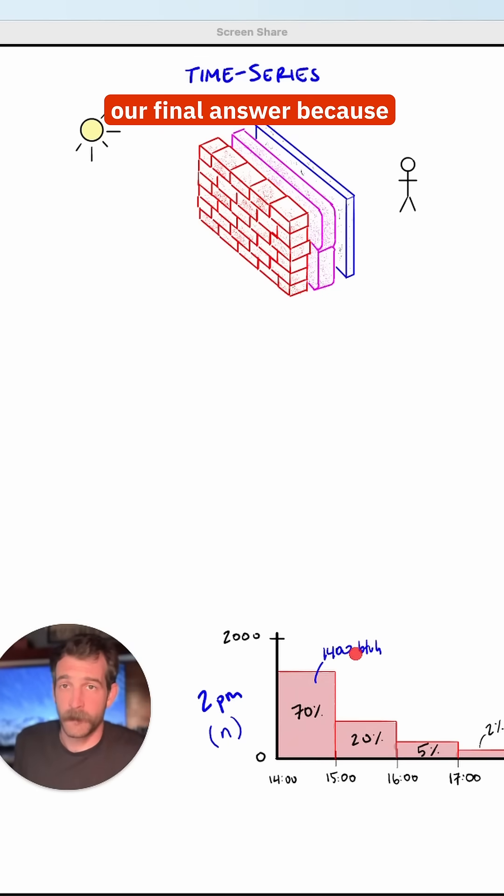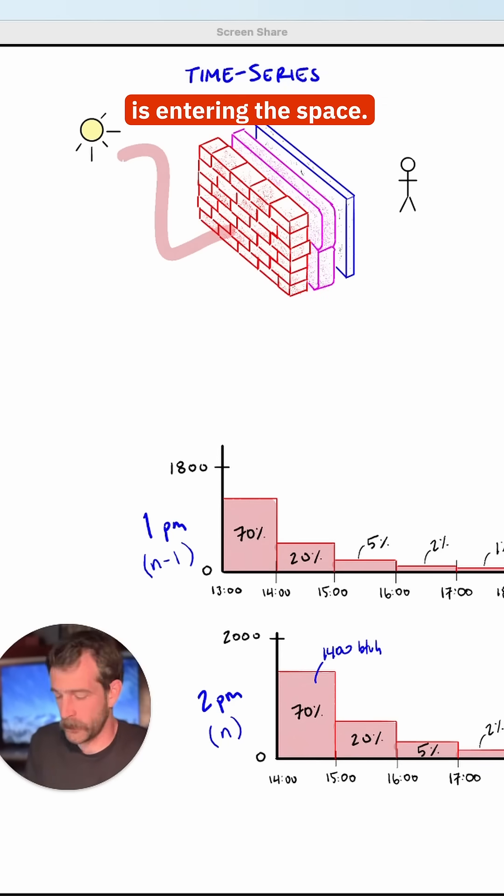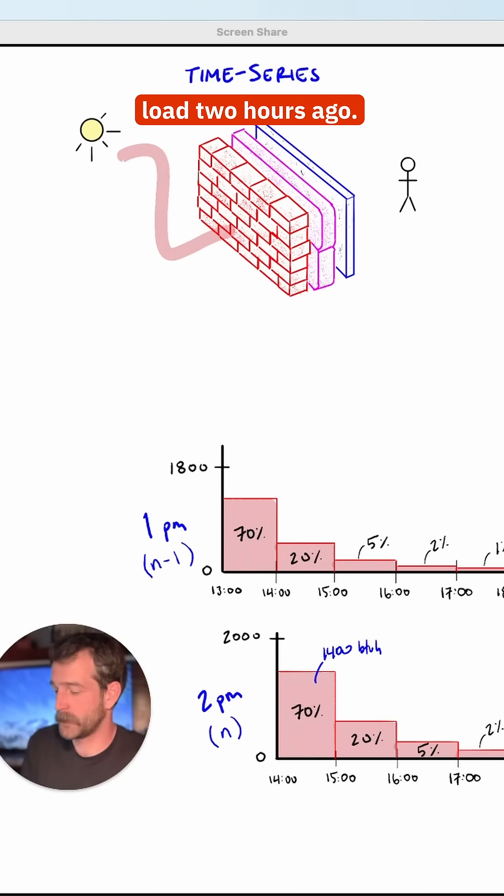But that's not our final answer because the load didn't just appear at 2 p.m. There was also a load an hour ago, and now a percentage of that load is entering the space. Likewise, there was load two hours ago, and a percentage of that is now entering the space.